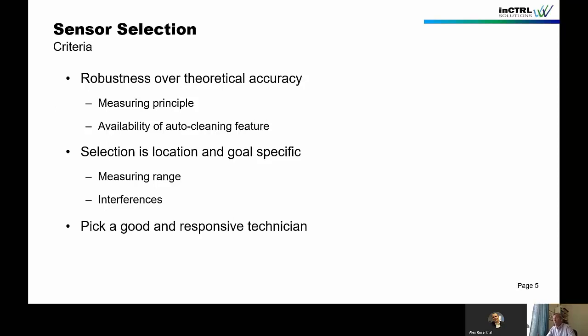We also go through all kinds of interferences with you in a structured manner, and that could include, for example, color, if you have a color sensitive measurement. One thing I always like to point out is that it's not just the instrument, it's also the service you can get. So one statement I often make is: pick a good and responsive technician, and that might actually be more important than having the perfect sensor.